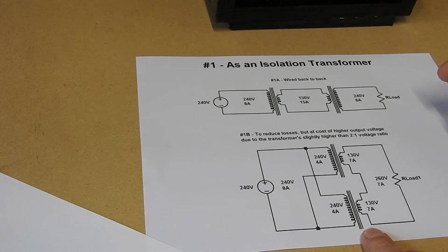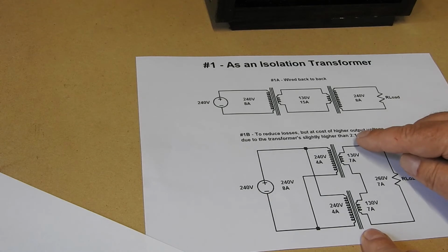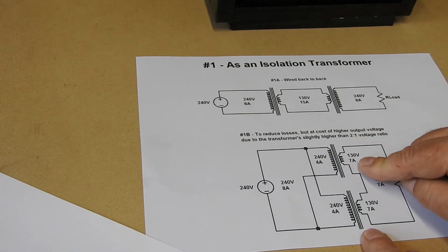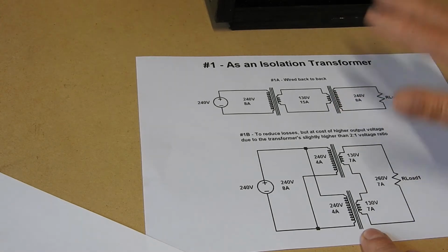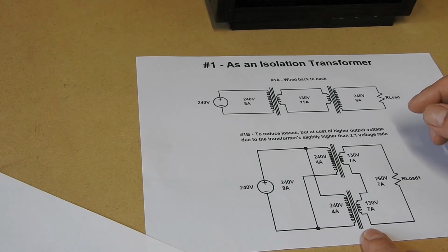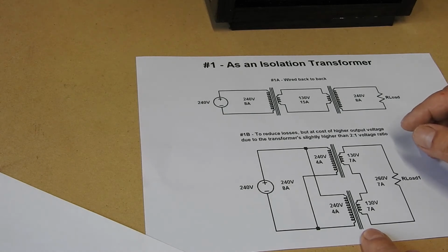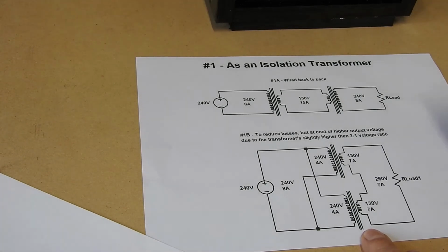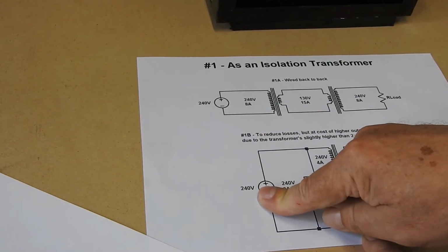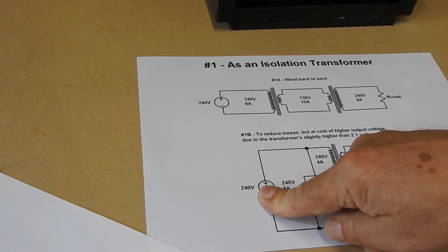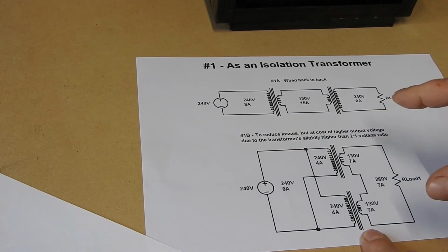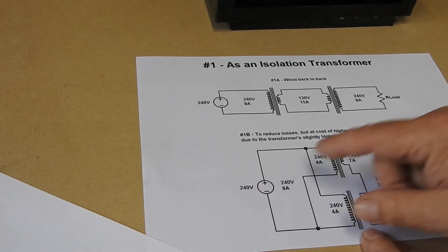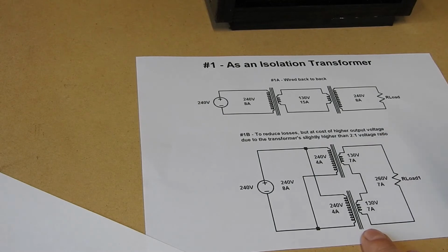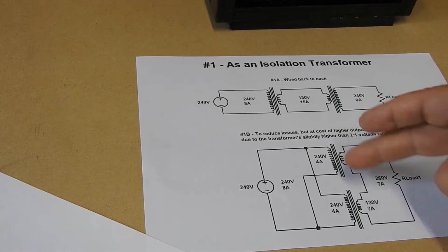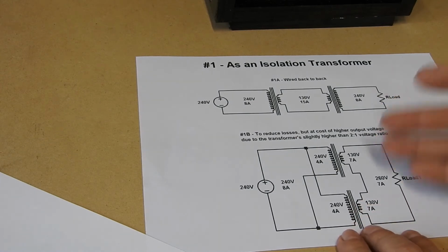Now, with these transformers, the problem is that they don't reduce by 50%. 240 comes out as 130, although under heavy load maybe that would come down to 120, but for lighter loads not so much. And it's especially a problem around here because I'm less than 100 metres from the main distribution transformer, so the voltages here are consistently around 250 volts rather than 240, or the nominal 230 that it's supposed to be. So if I put in 250, there'd be 270 volts coming out, which is probably a bit high for a lot of appliances. But it would be easier on the transformers and be less sagging. That'll be the way to go for heavy loads.